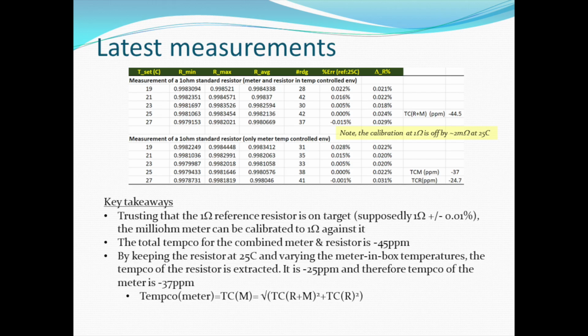So the total combined tempco for the meter and the resistor is minus 45 ppm, the topmost set of readings, and then by keeping the resistor at 25, I can extract the effect of temperature on the meter itself by using the formula below, which is the statistical effect of taking the sum of squares and square root of that. So we have the temperature coefficient of the meter to be around minus 37 ppm or so. I think that's pretty good, considering that the temperature varied almost 8 degrees over this, and typically in a room temperature environment this variation is probably reasonable, maybe a little bit higher or lower than this, but even if I didn't do anything, I think this will be fairly easy to live with. I could even compensate for this if I put in a formula for the slope of this particular equation for the error.